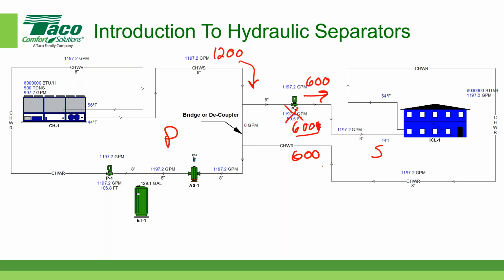And because we had 1,200 in the primary circuit, we're going to peel off 600. That means that across the bridge, we're going to wind up with 600 gallons per minute. So we're going to have 600 across the bridge here. And that 600 plus the 600 coming back from the secondary circuit is going to be equal to 1,200. So that is the case where the primary flow is greater than the secondary flow. So that's case number 2.